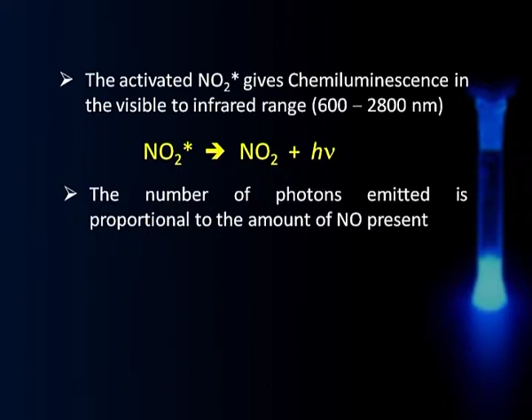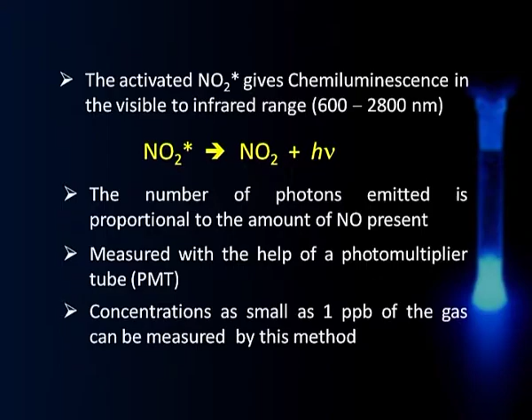So, this gives you the amount of NO present. The determination of NO is very straightforward. You put the sample into the reactor, it reacts with ozone and gives NO2 star, and in the second step NO2 star gives out a photon. Measure the number of photons, and that gives you the number of molecules of NO present in the sample. The photons emitted are measured with the help of a photomultiplier tube. This method is so sensitive that we can measure concentrations as small as about 1 ppb, that is, 1 part per billion, in a sample of polluted air.